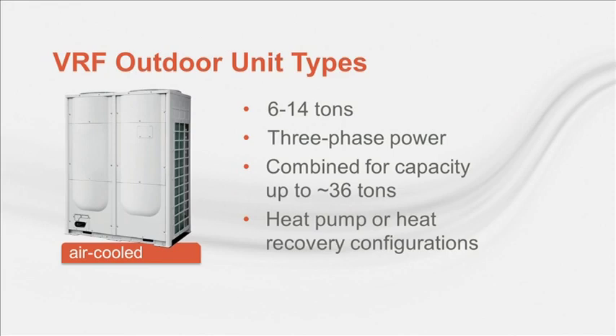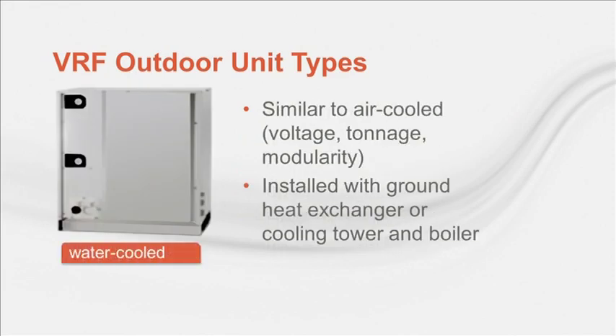Finally, VRF outdoor units are also available for water-cooled application. They are similar to air-cooled models with regard to voltage, capacity increments, and modularity, and are also available in either heat pump or heat recovery application. The primary difference is the outdoor unit uses water rather than air to exchange energy. Water-cooled units can be installed with either a ground heat exchanger or a cooling tower and boiler, and they can be installed either indoors or outdoors.